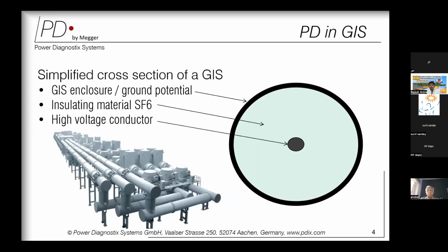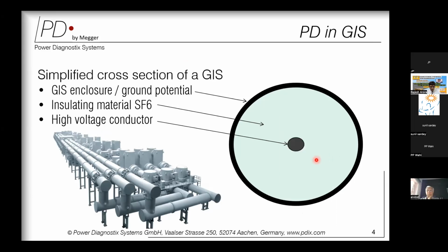Let's understand something about the basics of partial discharge. I will touch upon a few things because they will be discussed in the future. If we talk about the GIS, there are three important components. One is the central conductor or high voltage conductor. Then there is an outer enclosure, which is at ground potential. And between the conductor and the enclosure, it is filled with gas, which is the insulating material.